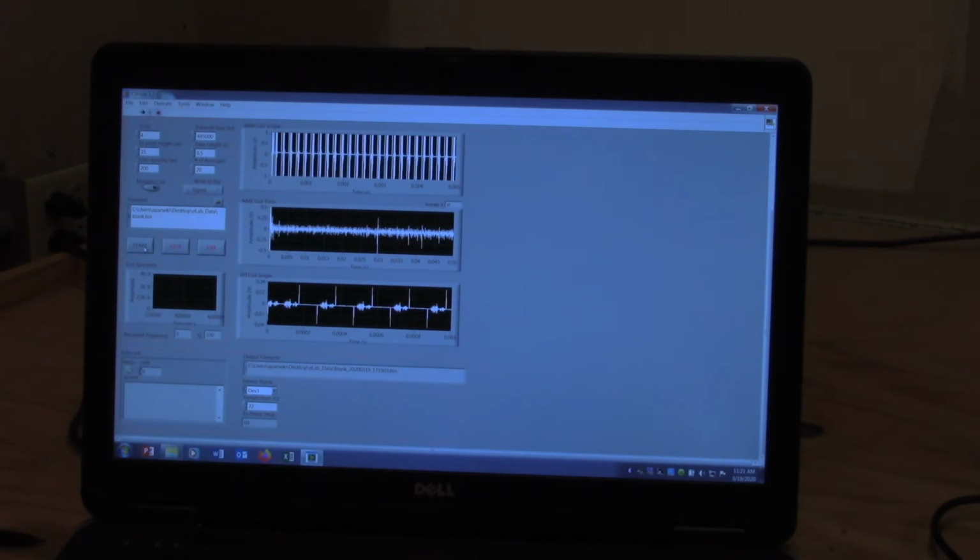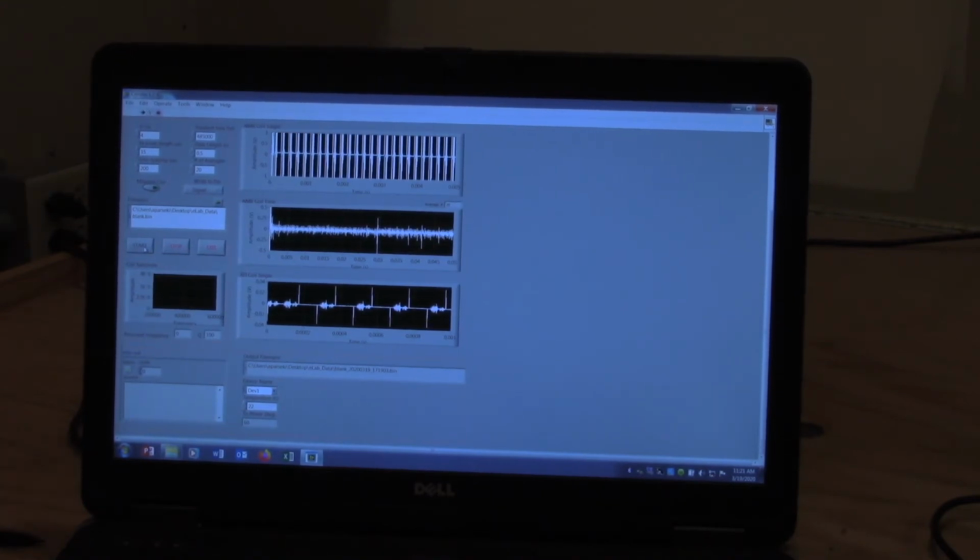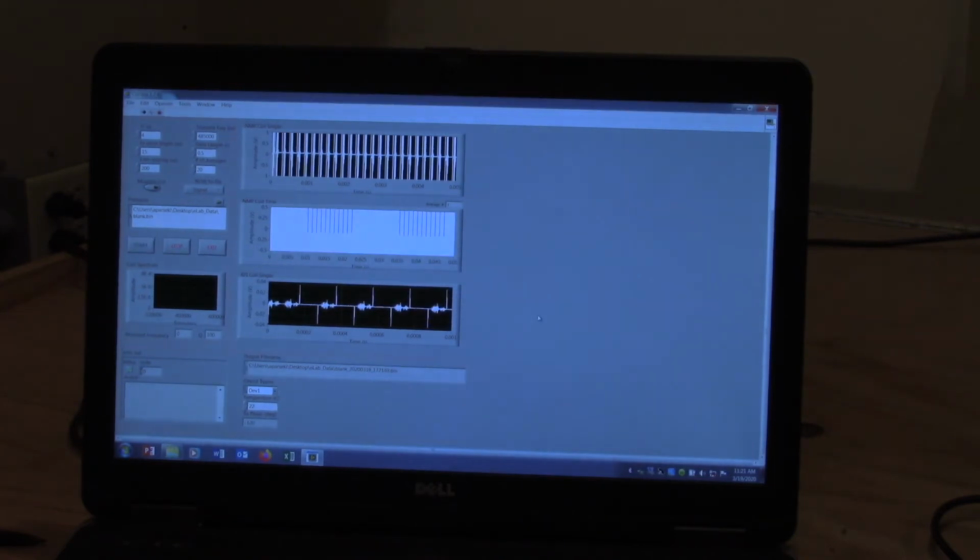So we have our sand sample in there, and we come back to the acquisition software. The only thing we're going to change is this TR, because it's a sediment sample. We don't need as long of a recovery time. So that's set. We can say run, and now we can just let it measure.